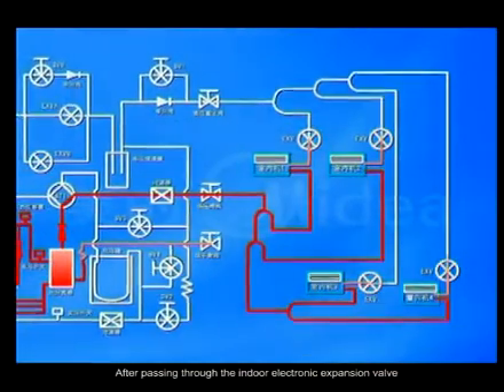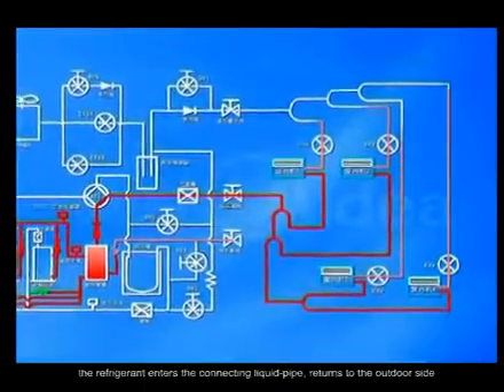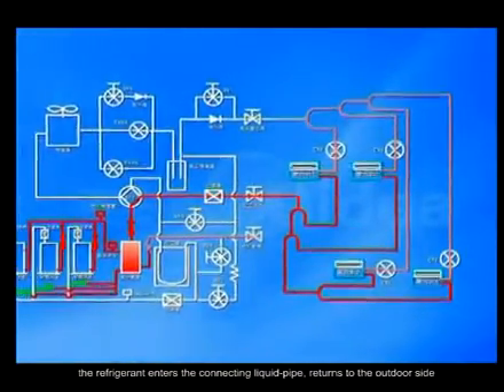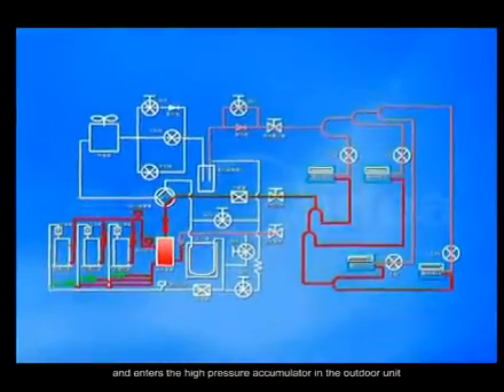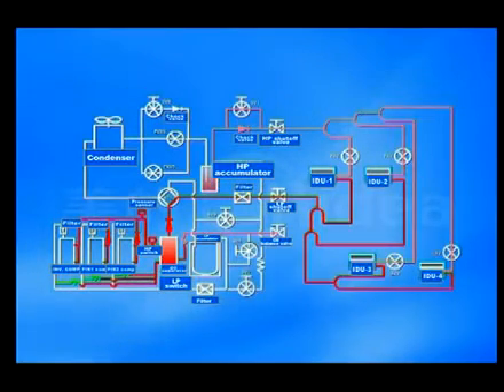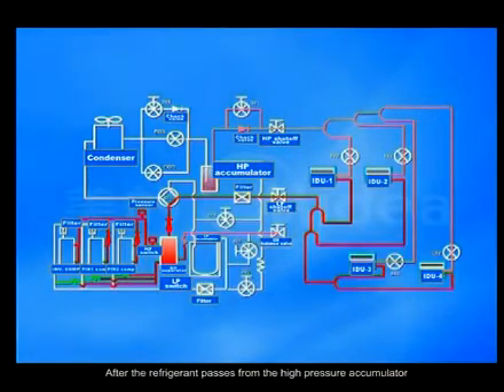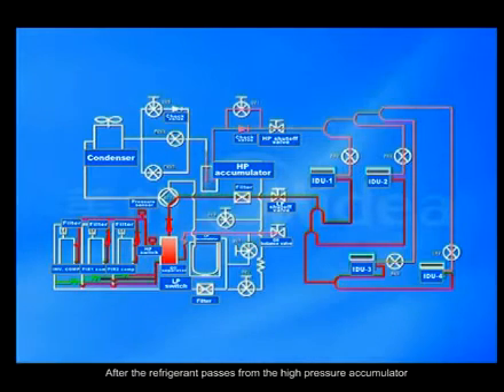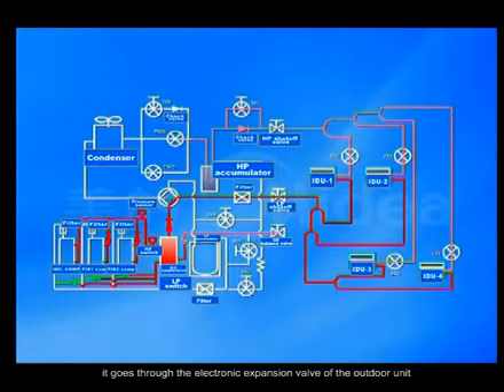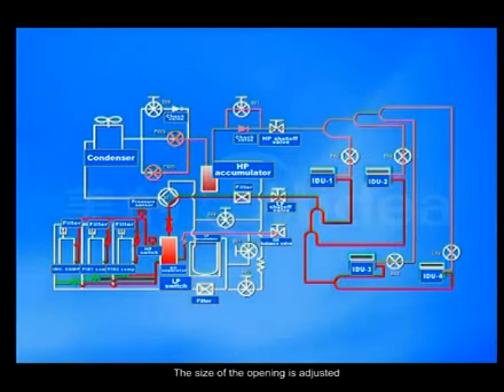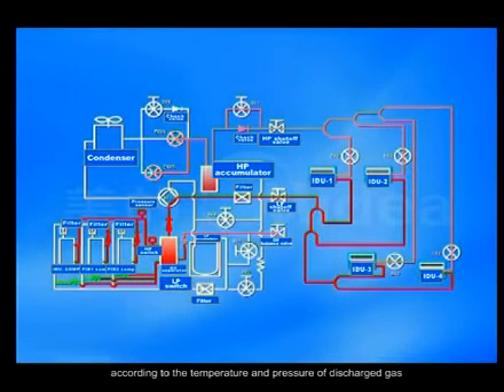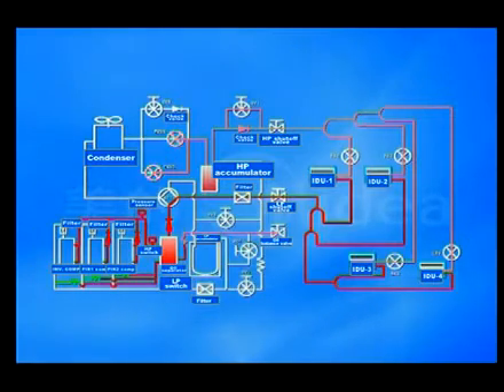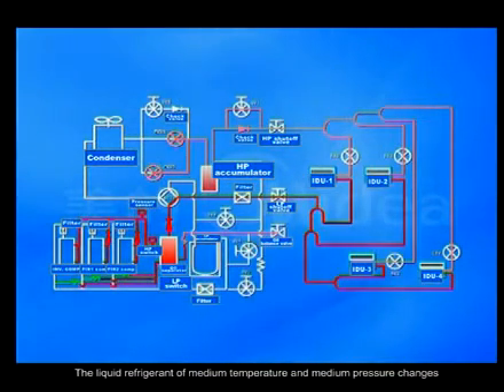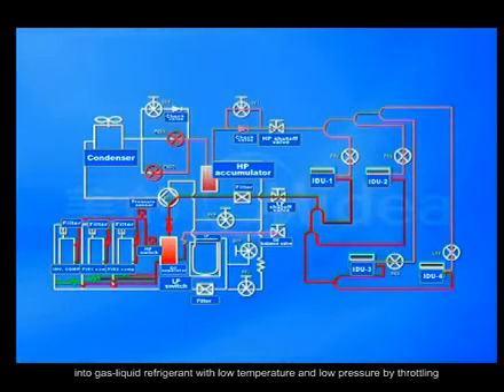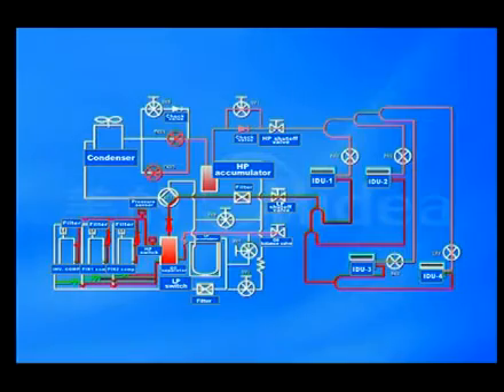After passing through the indoor electronic expansion valve, the refrigerant enters the connecting liquid pipe, returns to the outdoor side, and enters the high-pressure accumulator in the outdoor unit. After the refrigerant passes from the high-pressure accumulator, it goes through the electronic expansion valve of the outdoor unit. The size of the opening is adjusted according to the temperature and pressure of discharged gas. The liquid refrigerant of medium temperature and medium pressure changes into gas-liquid refrigerant with low temperature and low pressure by throttling.